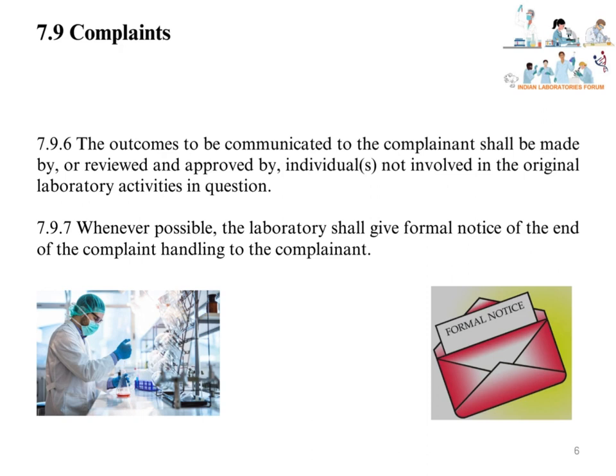The outcomes to be communicated to the complainant shall be made by, or reviewed and approved by, individuals not involved in the original laboratory activities in question. The laboratory has to perform the investigation on the complaint received, and the investigation should be done by a person who is not involved in the original laboratory activities in question. An independent person should perform, review, and approve the investigation outcomes.